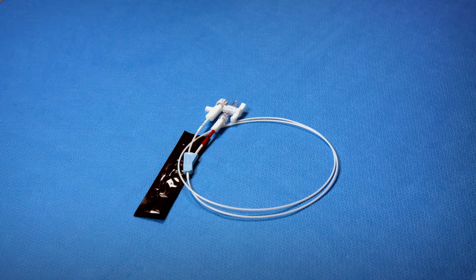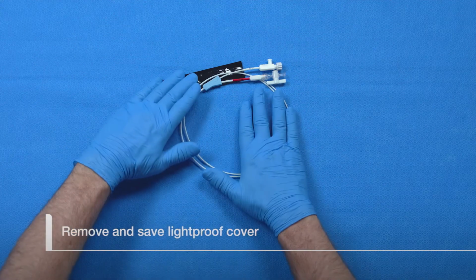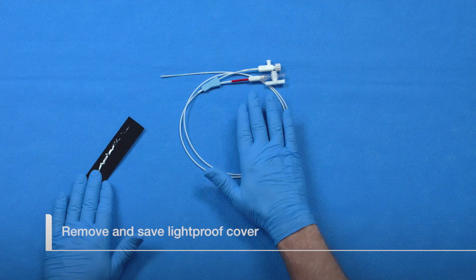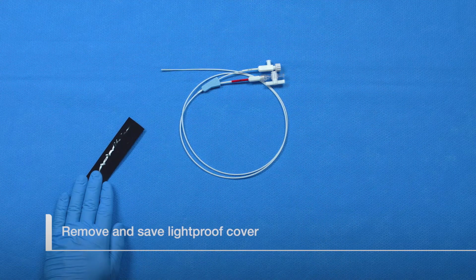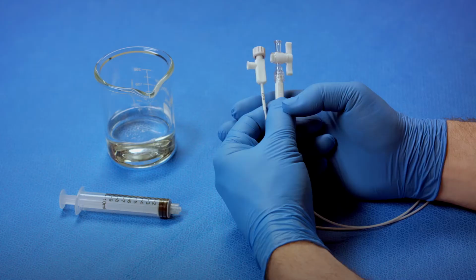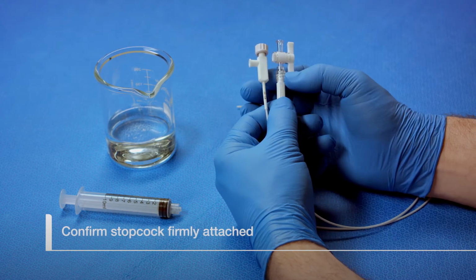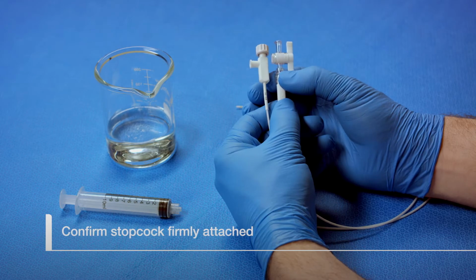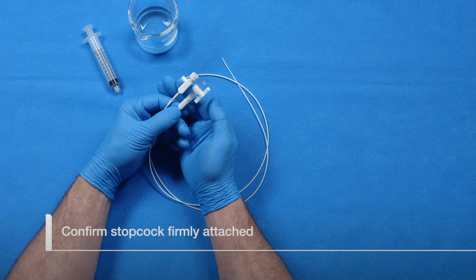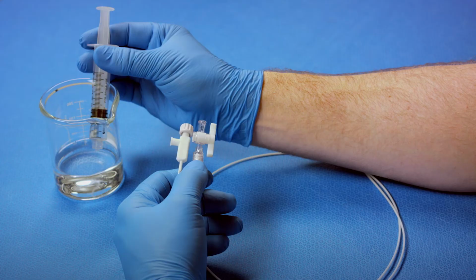To ensure that the appropriate valve size is selected for each targeted airway, the balloon catheter must be calibrated prior to its use. To calibrate the balloon, first remove the black lightproof cover from the balloon and set it aside, as it will be used later. Confirm that the stopcock supplied with the system is firmly attached. Do not over-tighten the stopcock, as it is possible to damage the luer fittings.